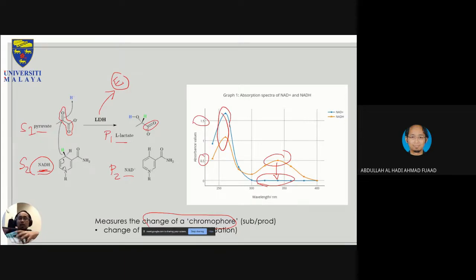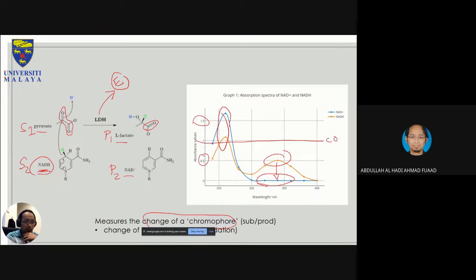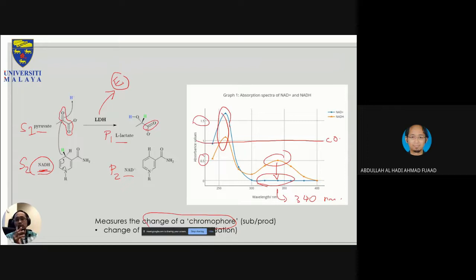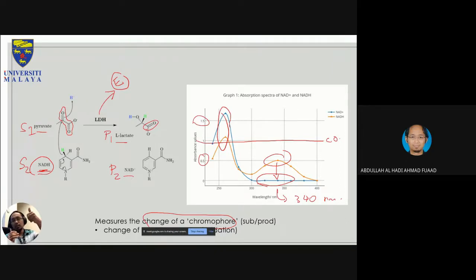If the spectrophotometer is high quality and brand new, it can measure above absorbance of 1, but normally you focus on values below 1. With a cut-off of 1, the wavelength between 300 to 400 nm is best. Looking at the lambda max, it is roughly 340 nm — the wavelength at which you see the greatest change in absorption of either the disappearance of the reactant or appearance of the product. The change from NADH to NAD⁺ is an oxidation process and is an example of chromophore change.